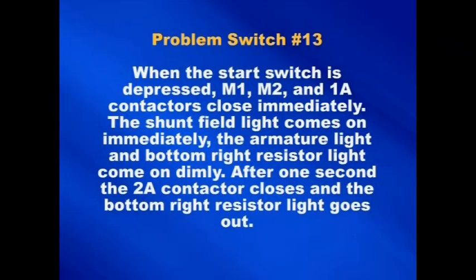And that's that. Should the apprentice electrician draw problem card number 13 on his test, it'll read as follows. When the start switch is depressed, M1, M2, and 1A contactors close immediately. The shunt field light comes on immediately, and the armature light and the bottom right resistor light come on dimly. After 1 second, the 2A contactor closes and the bottom right resistor light goes out.